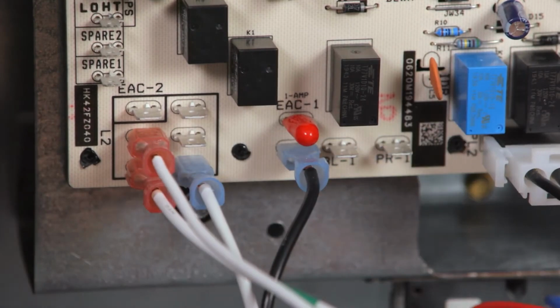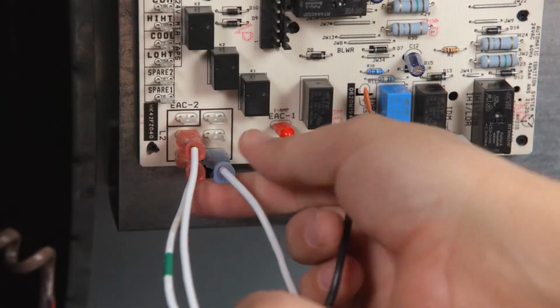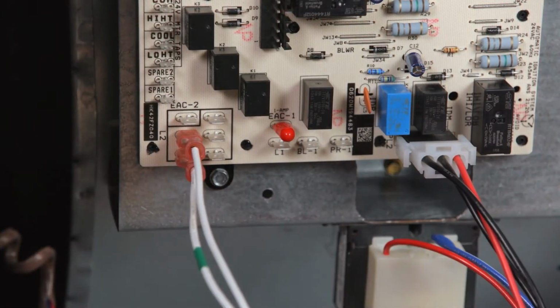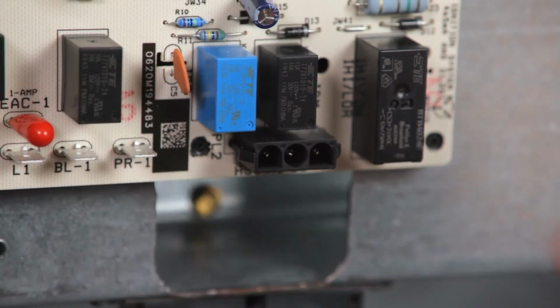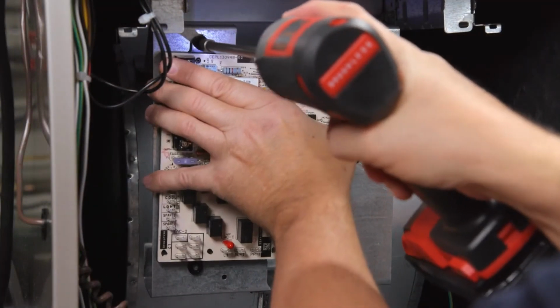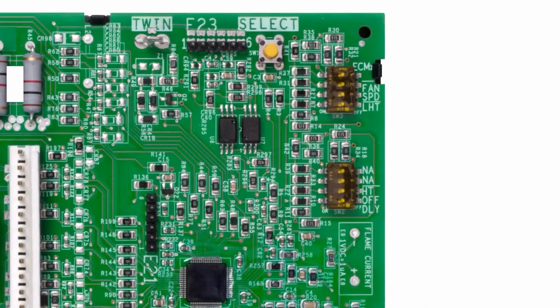Disconnect the blower motor 120-volt power and neutral wires. Remove the 120-volt power and neutral wires. Disconnect the 3-pin Molex hot surface and inducer plug and neutral wires. Finally, remove the board. Dip switches control the furnace blower settings.